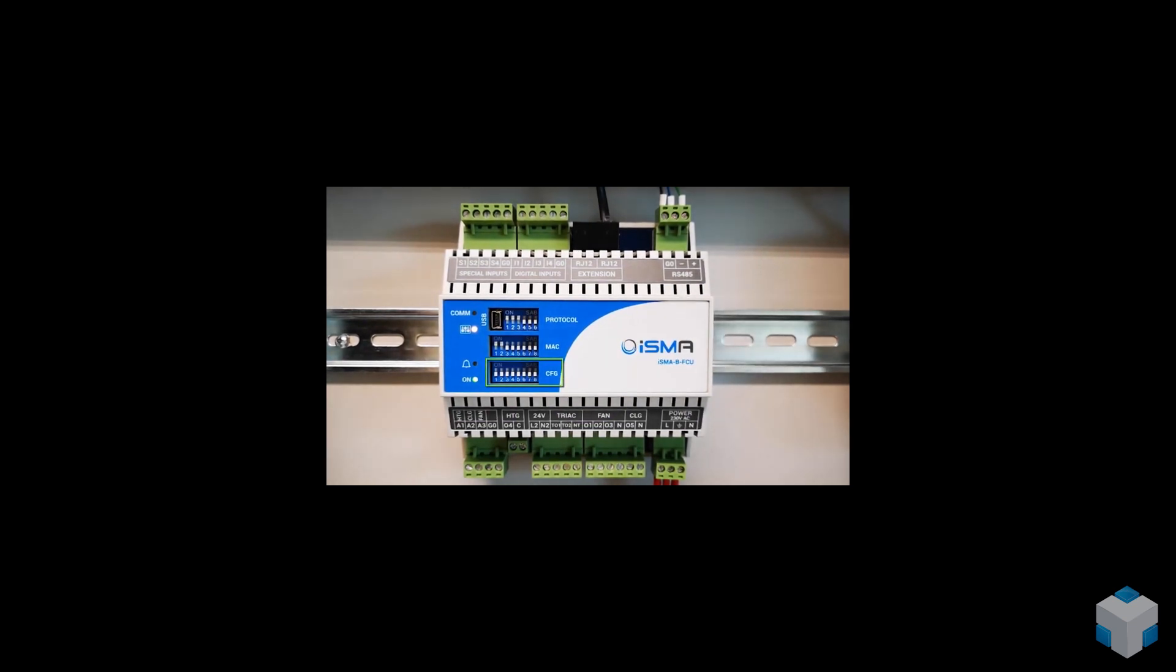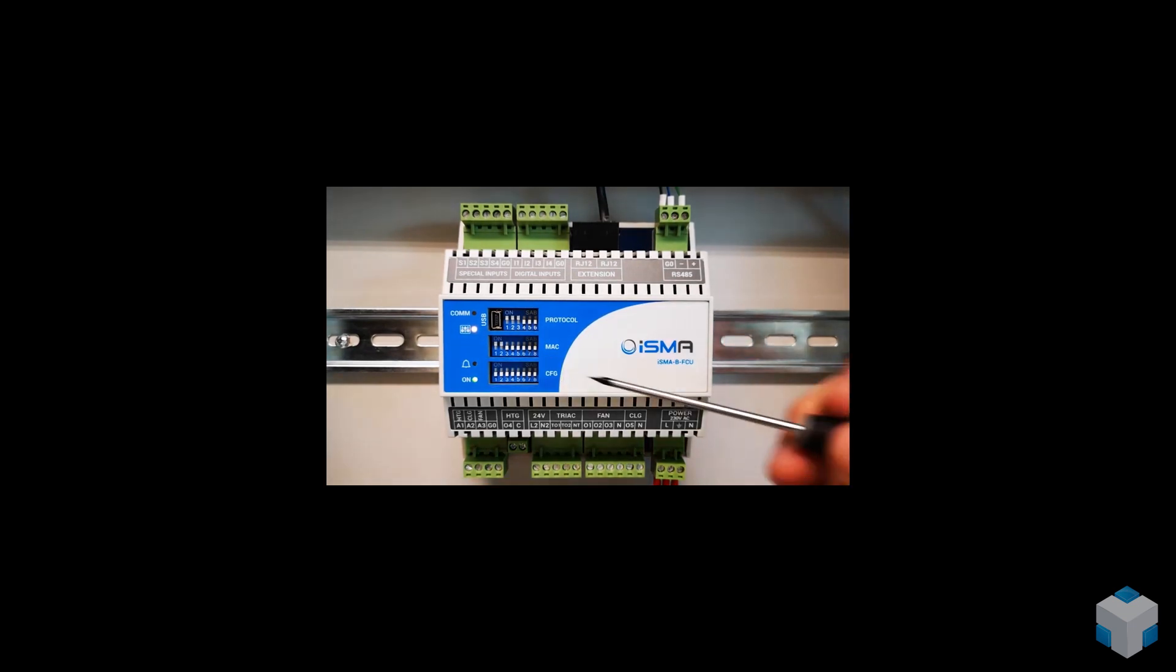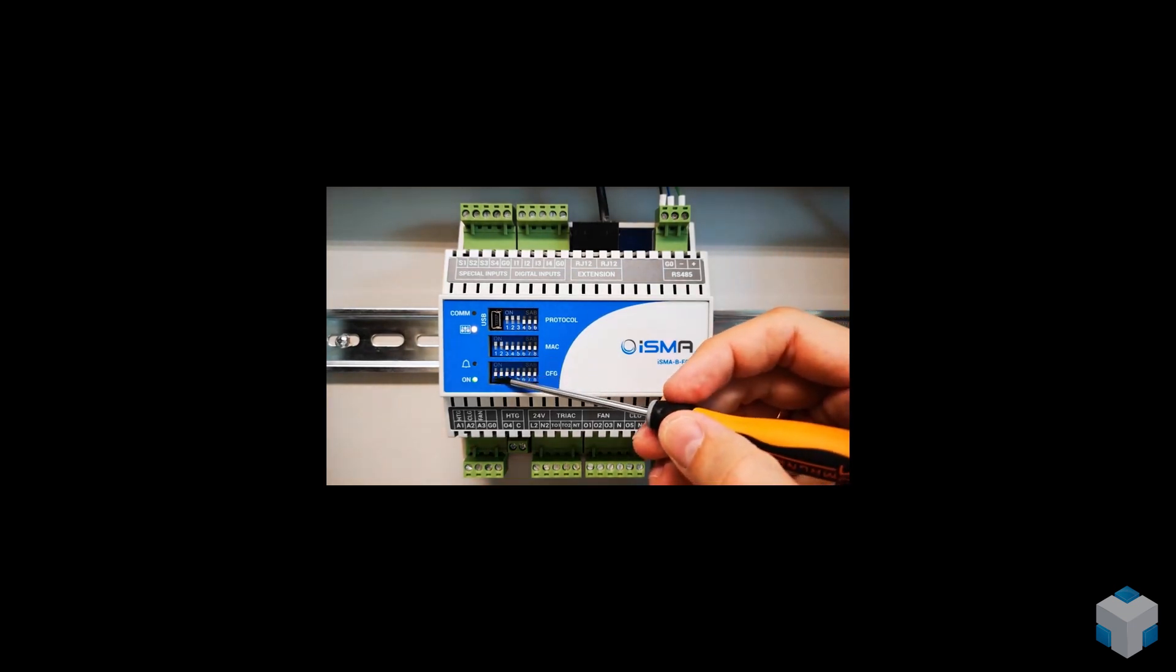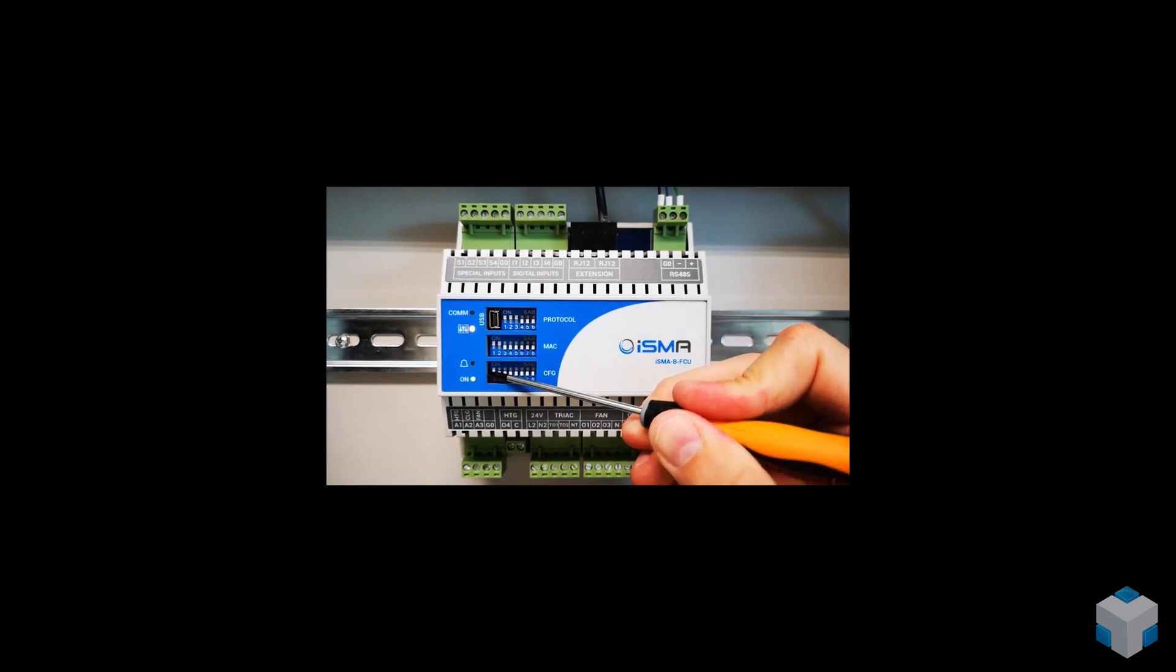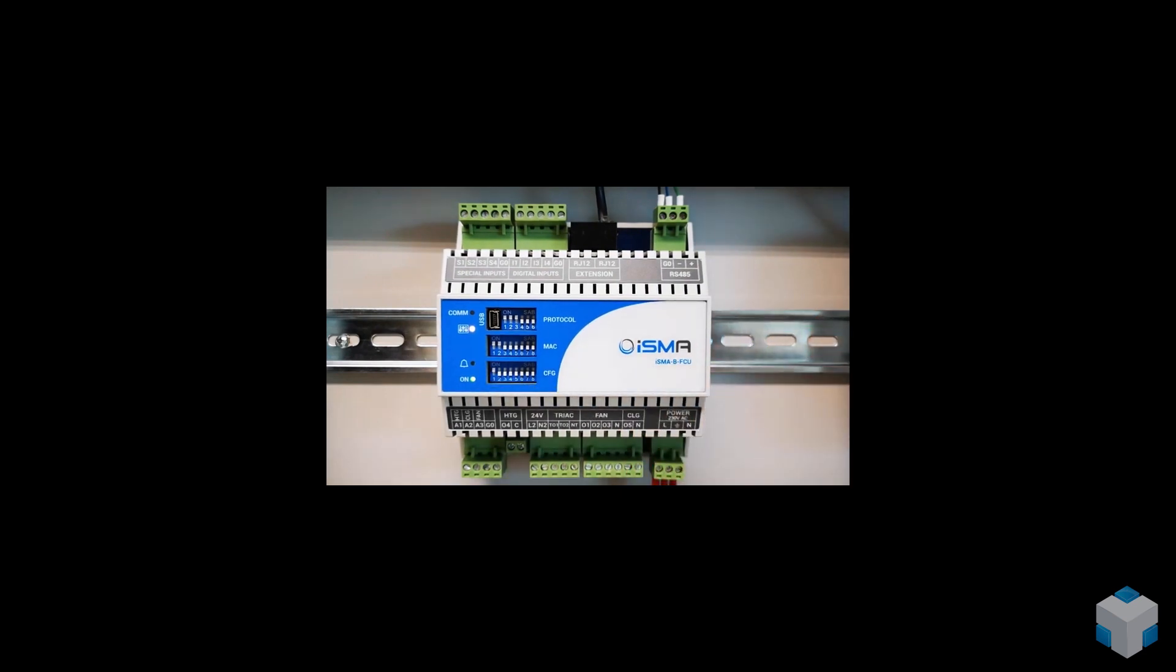Application adjustments are made with an eight position configuring DIP switch. The first DIP switch can choose the fan coil unit type between two-pipe and four-pipe water system.